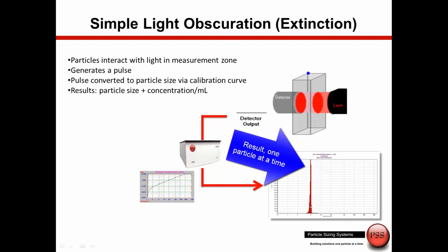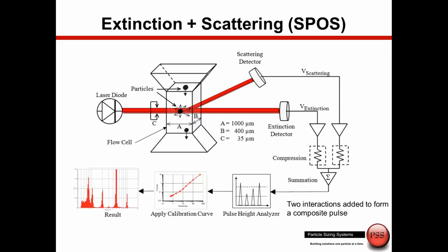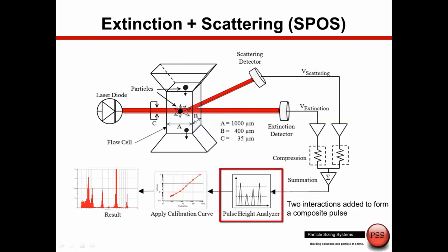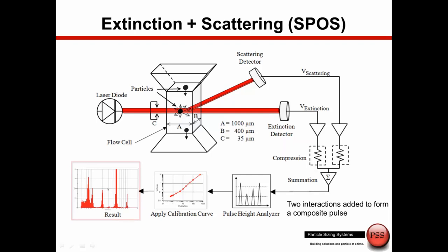We count and size these particles and build this distribution one particle at a time. The first improvement with the sensors created by Particle Sizing Systems is the addition of the scattering detector. Here we have the extinction detector, and here we have the scattering detector. We take these two pulses, sum them together, feed that combined pulse into the pulse analyzer, and then through the use of the calibration curve build up the results one particle at a time.